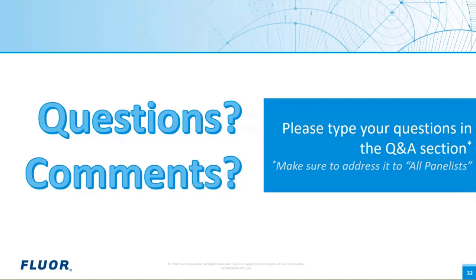I knew that was going to come up, and actually that's part of the reason why we're doing this presentation today, because this rule change did not actually go through the normal NFPA required process. What happened was there was a similar public input that was made, and then code panel one revised it during the time between the public input stage and the public comment stage, and therefore it did not undergo the full review process that normally would happen. So it's a little bit strange here.